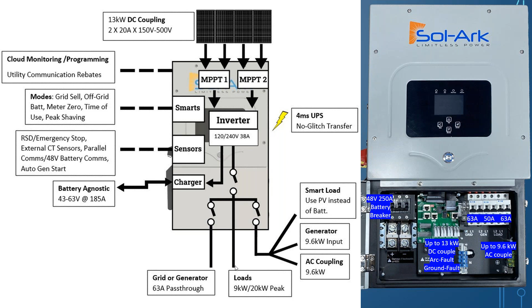So when using a Sol-Ark in an AC coupled situation, you can see what the AC coupled system size is, and based on that, expand the solar array using the DC MPPT. Yes, that's correct. We also have a tool on the website where you can plug in what you already have on your house if retrofitting, or start from scratch and plug in what you'd like, from the type of panels used on the DC side through to the AC coupled sizing, and it'll tell you if it'll work or not.